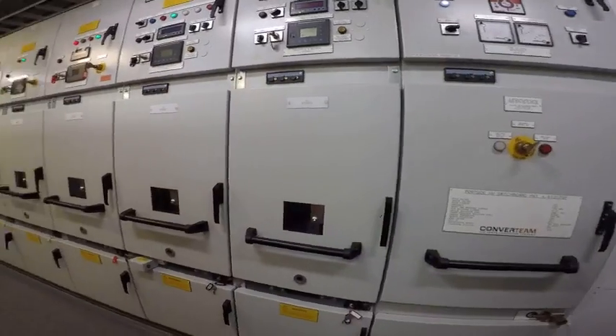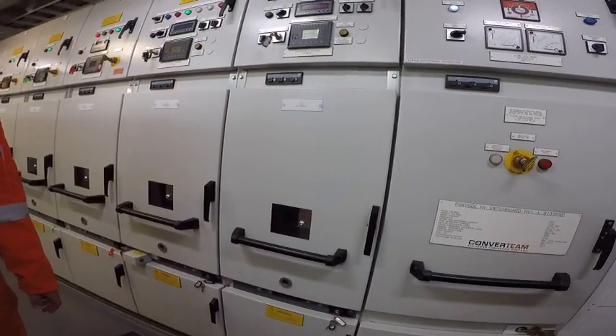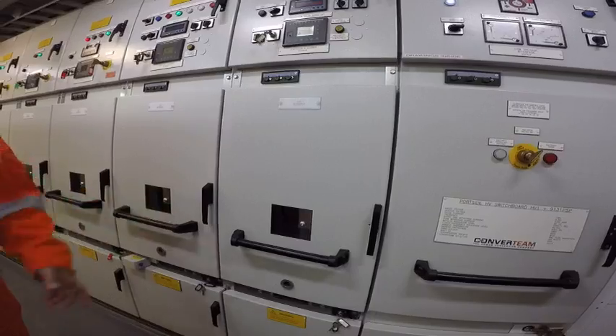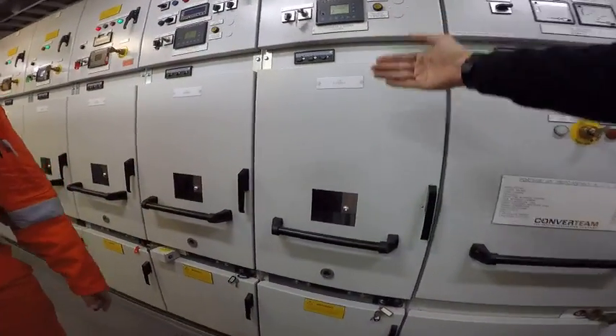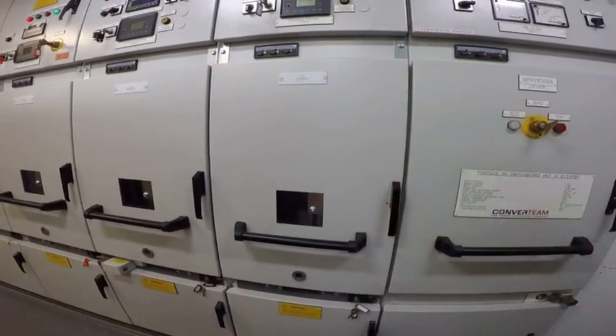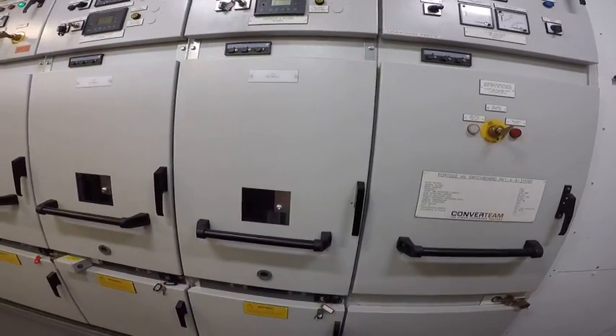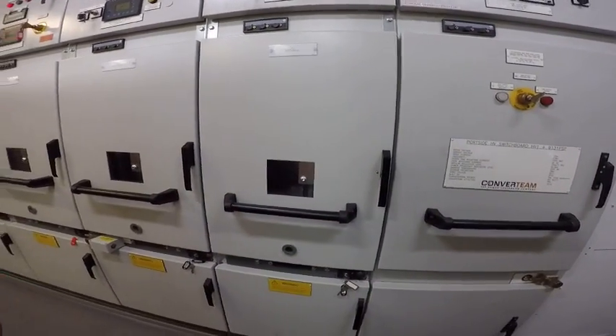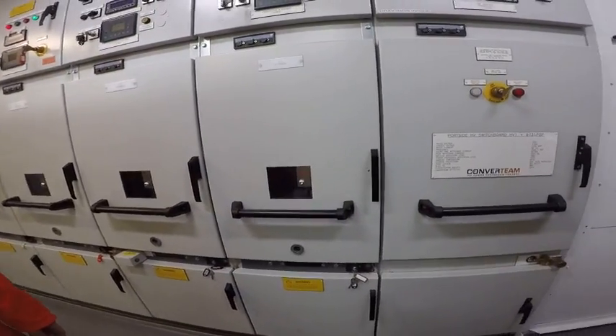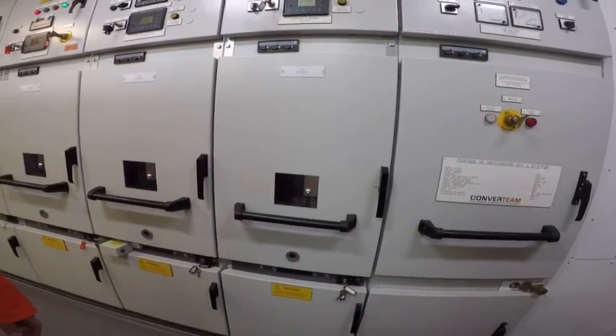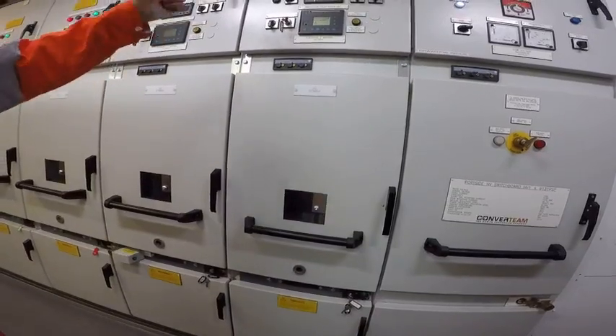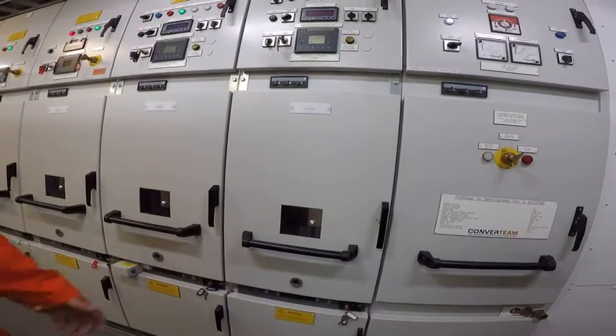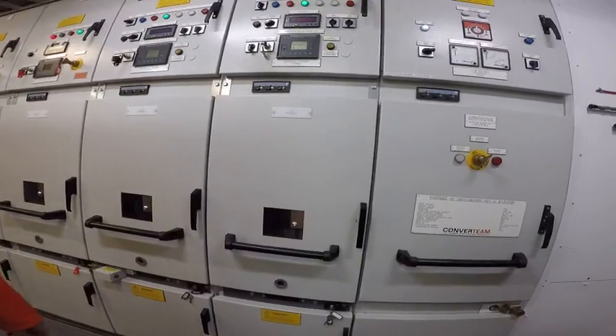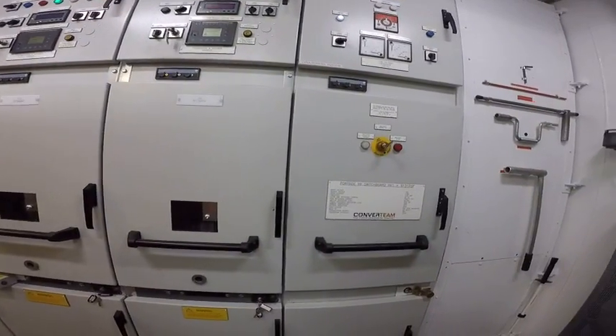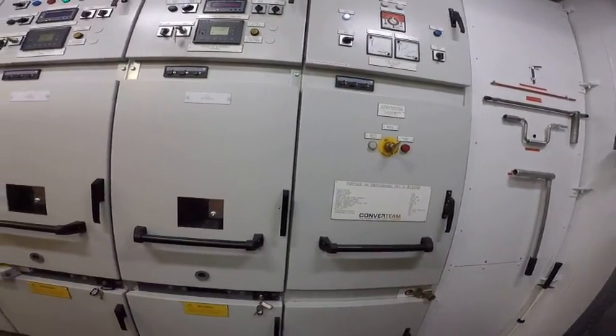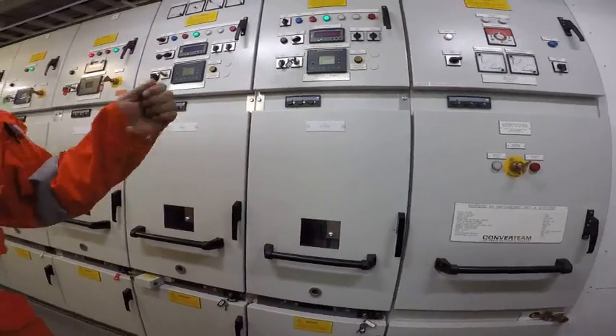Have you got the suit? No, we don't have the suit. We've got the racking out for it. So this enclosure can handle explosion and all that? It's supposed to, that's why you've got your protection mats down here as well. Because racking can be very dangerous, so you need to make sure it's off, nothing supplying, then you can rack out. There's a lot of interlocks on here, so you can't just do it - you need to have a key, or something, before you can do something.